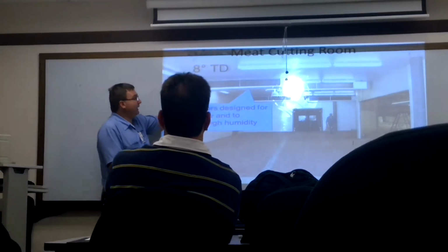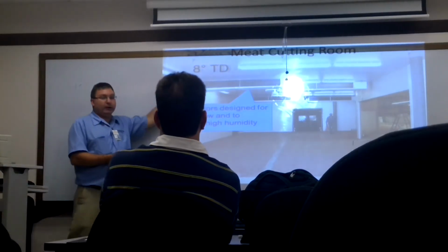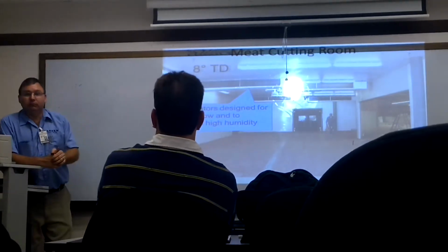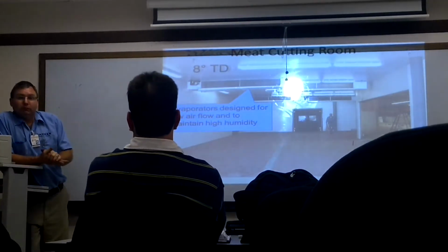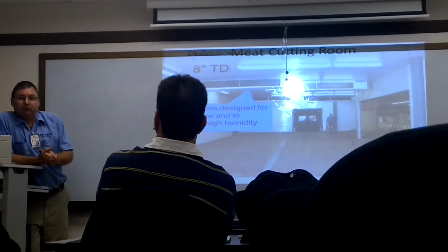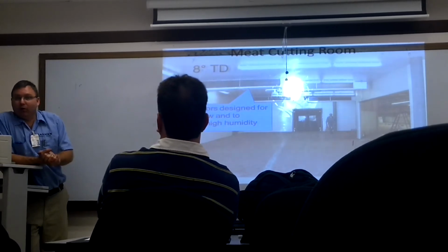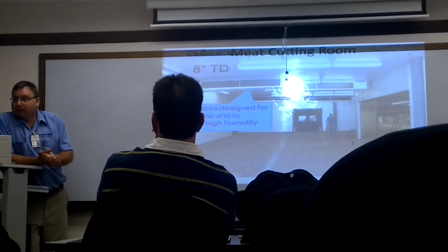So we got lower TD here. If we got a lower TD, are we going to have lower humidity or higher humidity in a meat cutting room? Higher. No, lower. No, higher. The higher the TD, the lower the humidity. The lower the TD, the higher the humidity.